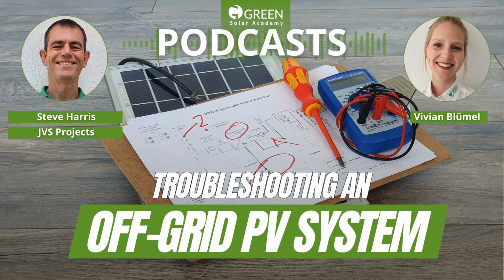Once we close the PV side, we can see what the charge controller is doing, whether it's integral in the inverter or a separate one. We have our DC tong testers, clamp meters, and have a look at what's coming off the roof or out of the array. Is the current coming into the charge controller from the panels what you should be expecting? If not, it's an indication that there's a problem on the array.